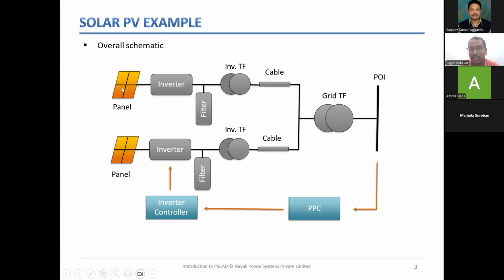So it converts DC into AC, and because it has switching based power electronics, your IGBT, it will have non-linear components in the output, and those we call harmonics, right? Interharmonics, characteristic harmonics will be present in the output of the converter. So we will require certain filters that will filter these out and give us a near sine wave. And then the converter typically operates at around 0.69 kV at the low voltage interface.